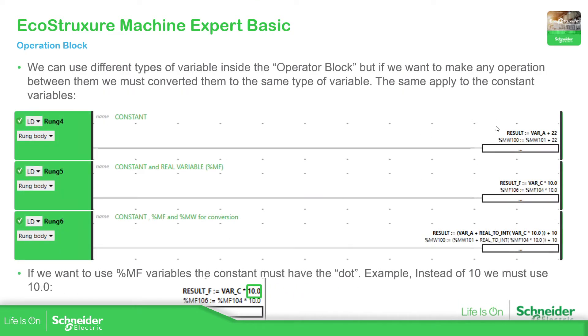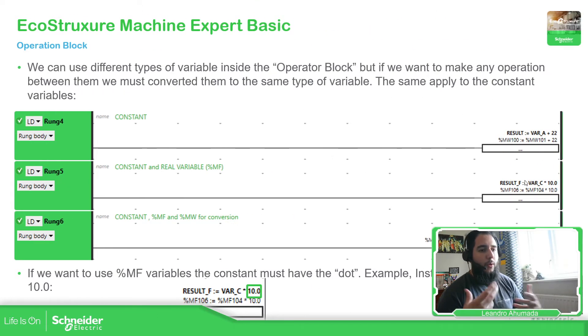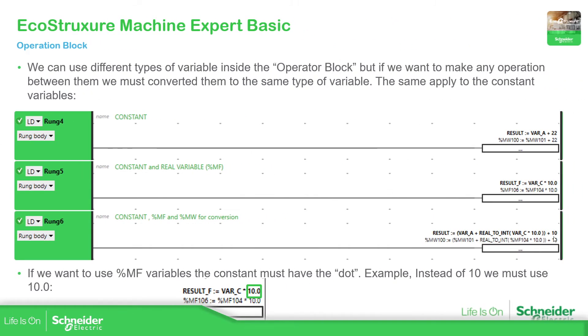Here you can see how I add different kinds of variables. I'm using a variable and a constant, and here I'm using a real variable multiplied by 10.0. This is important: when you use float variables, make sure it has the decimal point. So if you're using constant values, add the decimal point. Here is a complete structure with a mix — I'm adding variable A to variable C which is a float variable, and I use a converter, real to int, on this operation.